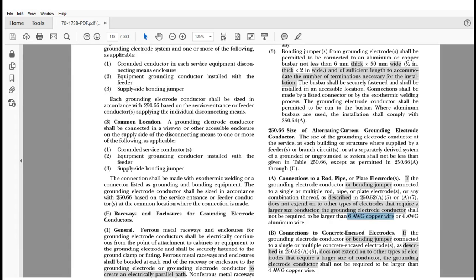They assume that it means that bigger is better. At the end of the day, the ground rod can only handle so much anyway, right? So it's like pulling 10 gallons of water in a 2-gallon bucket. It's not going to happen. But we have the provisions here. The important part here is if I go from ground rod to ground rod to ground rod to ground rod, they don't have to be larger than a 6. That's it. If I go from rod to pipe, it doesn't have to be larger than a 6 copper or 4 AWG aluminum.